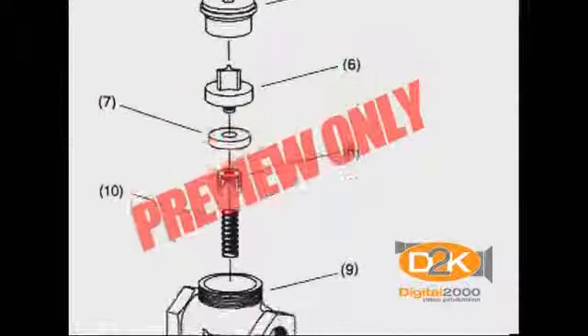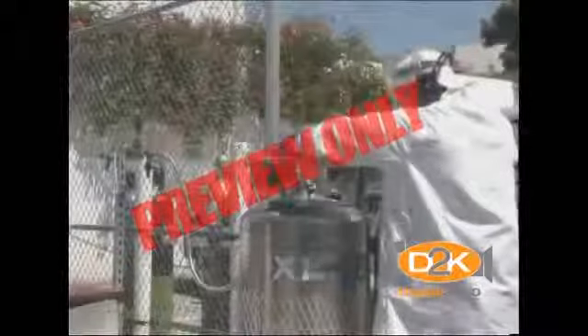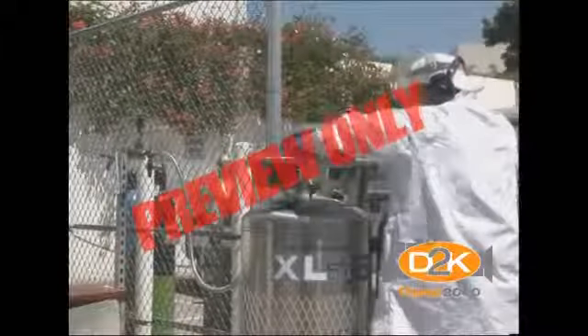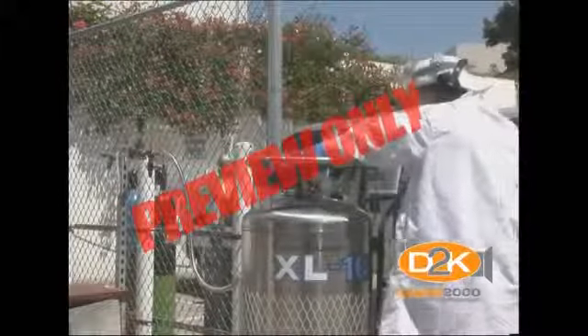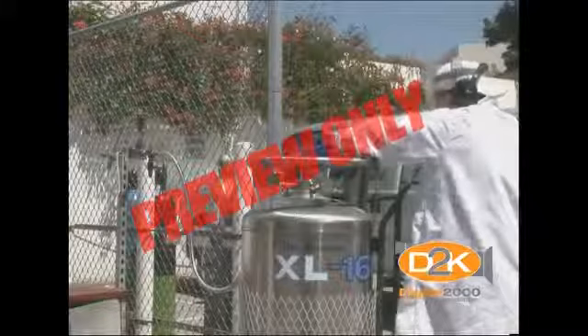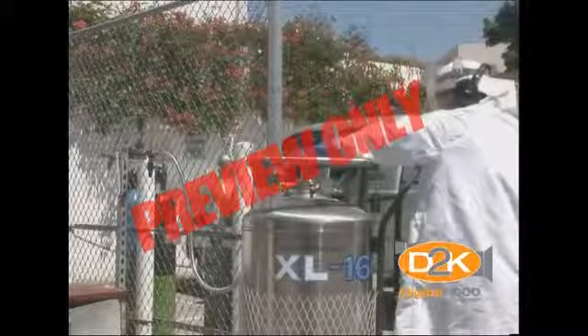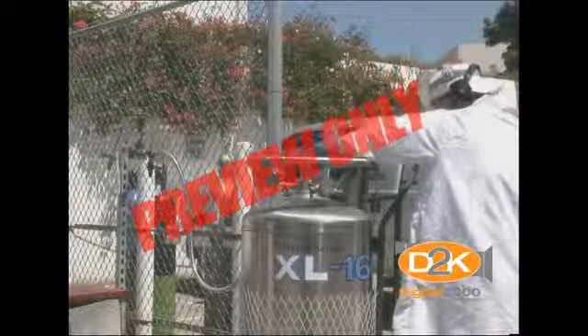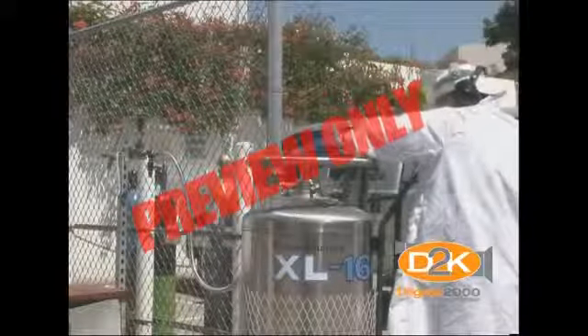Some valves may require washers. This should be checked before the regulator is fitted. Cylinder valves should be opened slowly, and always make sure that cylinder valves are opened all the way. Open the oxygen cylinder valve stem just a crack. Once the needle on the high-pressure gauge has stopped, open up the valve all the way. This prevents the high-pressure gas from leaking out through the threaded stem.